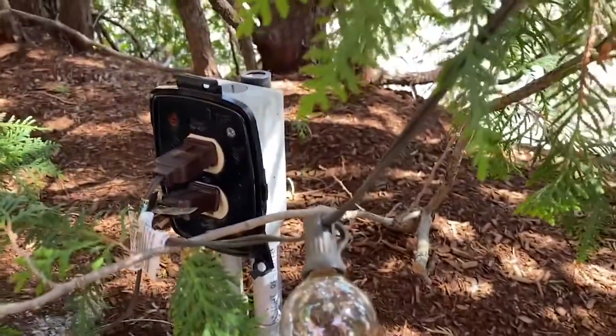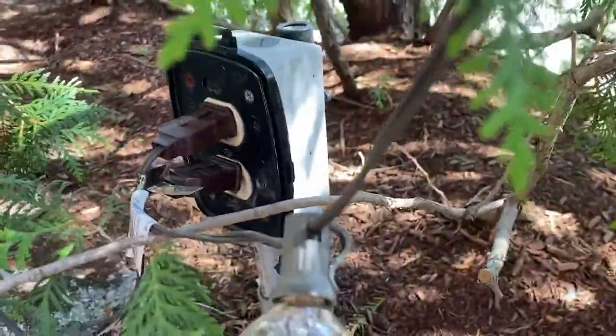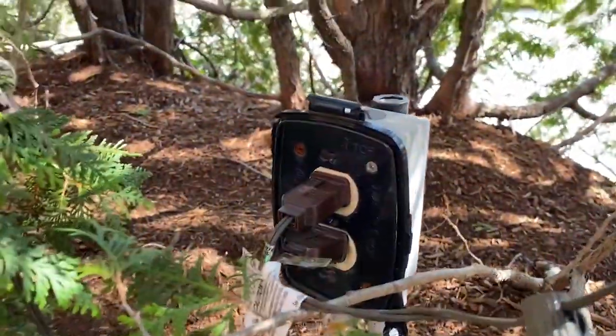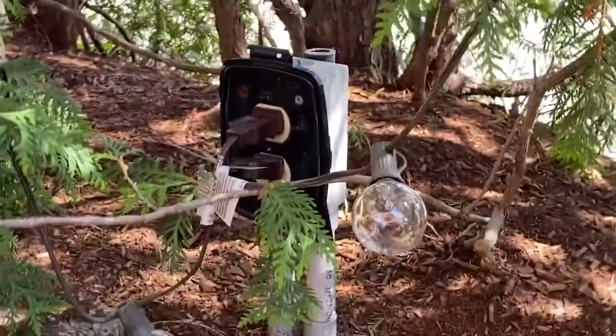Welcome to Moving Violations. This is Russ LeBlanc, NEC Consultant for EC&M Magazine. I'm presently sitting in an outdoor dining area at a restaurant, and I spotted this — the cover is broken, and so that's a violation of section 110.12b.